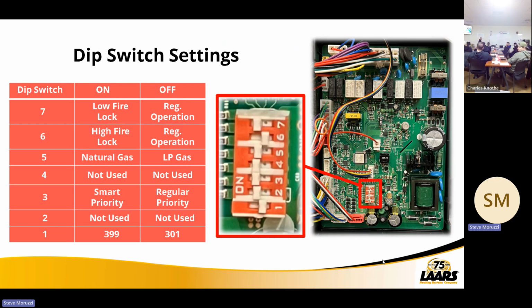So again, smart priority is done on modulation. Traditional priority would be, if I have a domestic demand, I'm only going to operate that boiler in DHW until I satisfy the indirect tank. Then I'll go back to heating. Does that make sense? Does that have a time on it? No, not in smart priority, no.